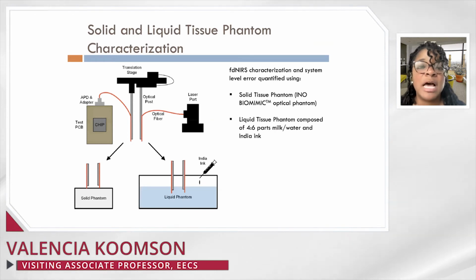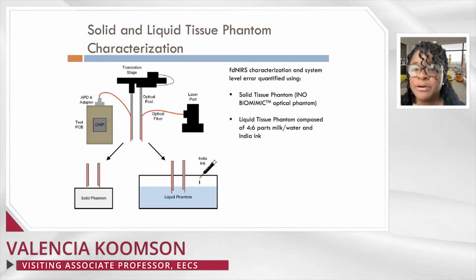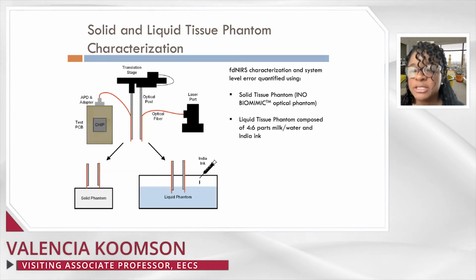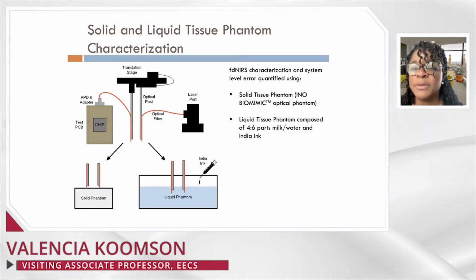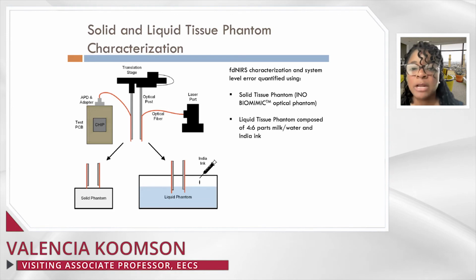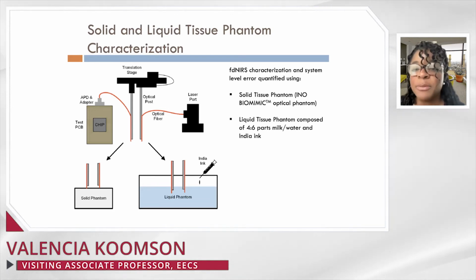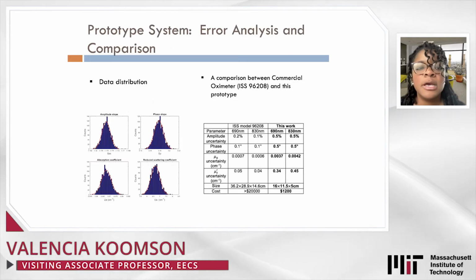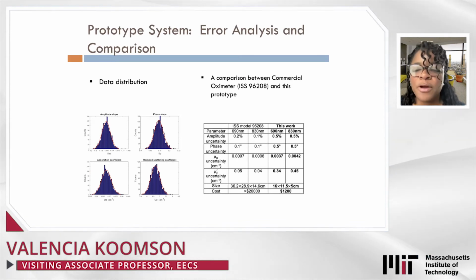We have carried out characterization of our ASIC designs using both solid and liquid tissue phantoms. For frequency domain NIRS, the system level error is quantified using both a solid tissue phantom with calibrated absorption and scattering parameters, and a liquid tissue phantom composed of milk, water, and India ink, which mimics the absorption of oxygenated and deoxygenated hemoglobin. Characterization results show results that are comparable to a commercial oximeter.